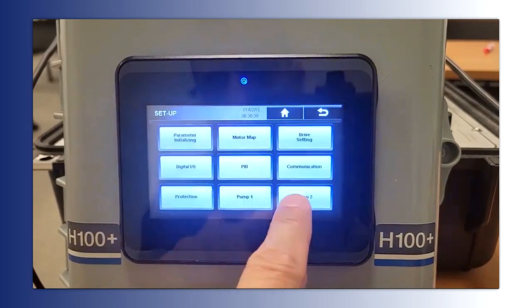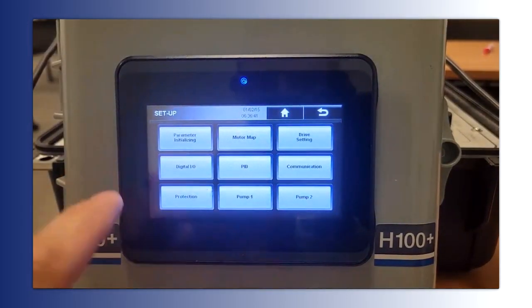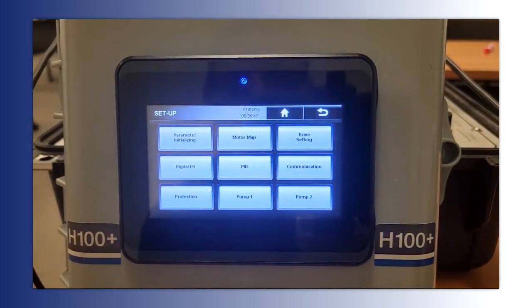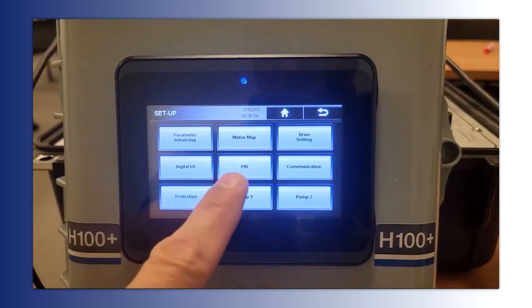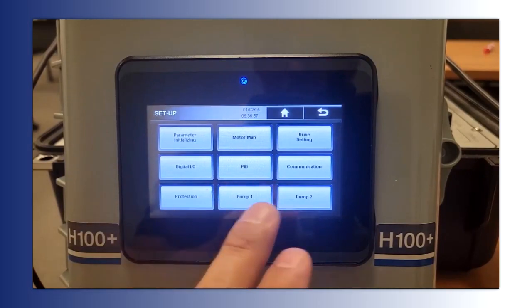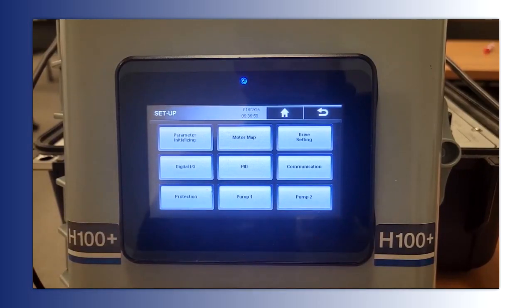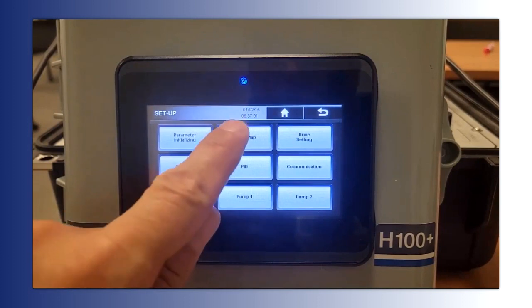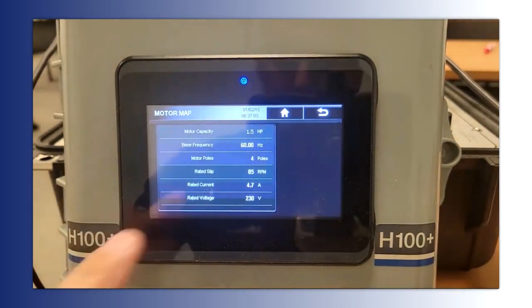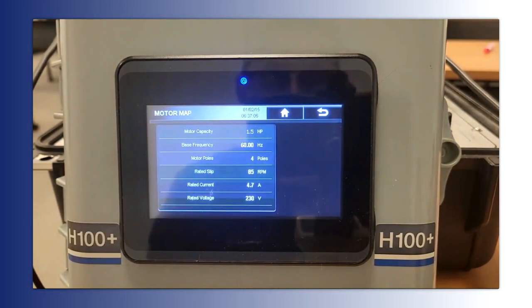You have setup. And what we did is we broke down the common parameter groups into these buttons right here. So parameter initializing resets the drive. Here's your motor parameters, we mentioned that. Your drive setting parameters: how do you start, how do you stop, your I/O, your PID, pump protection, and then additional pumping settings in pump 1 and 2. So if I go to our motor map, you can see this is set up for a 1.5 horsepower motor, 60 hertz, the motor poles, the RPM, the rated current, all the stuff we already discussed.